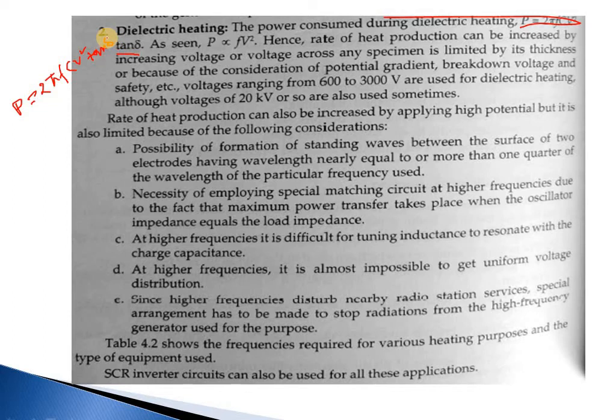As seen, P is directly proportional to F. Hence, the rate of heat production can be increased by increasing voltage, but the voltage across the specimen is limited by its thickness, or because of the consideration of potential gradient, breakdown voltage and safety etc. Voltages ranging from 600 to 3000 volts are used for dielectric heating. Voltages of 20 kV or so are also used sometimes.